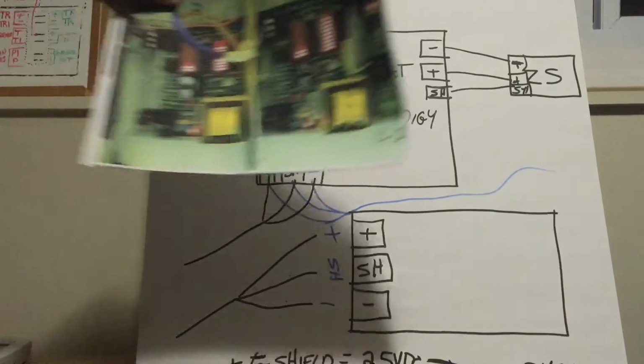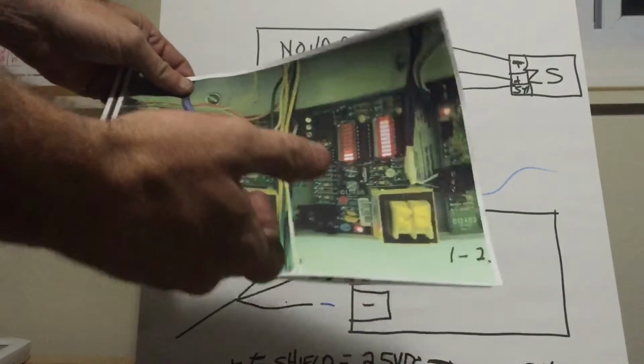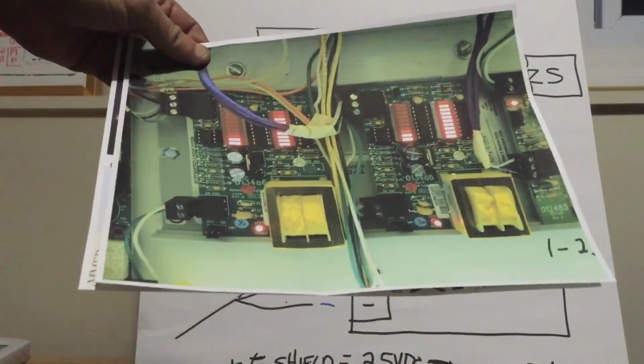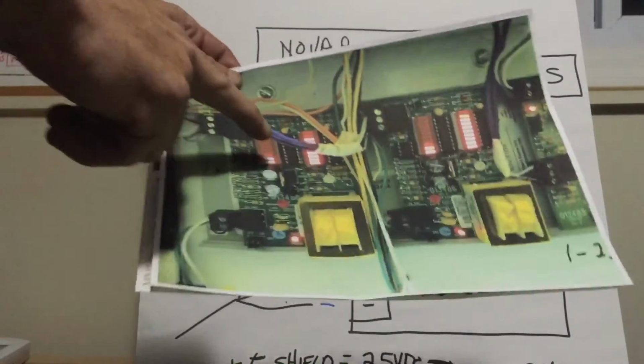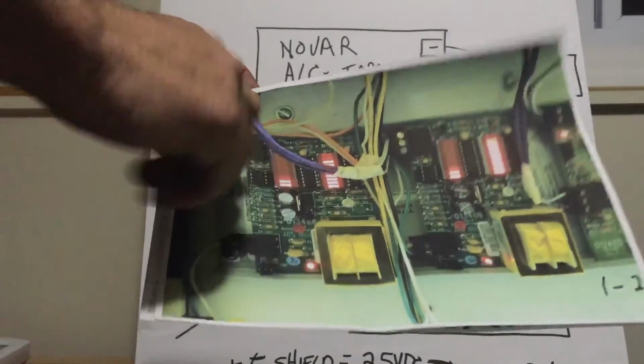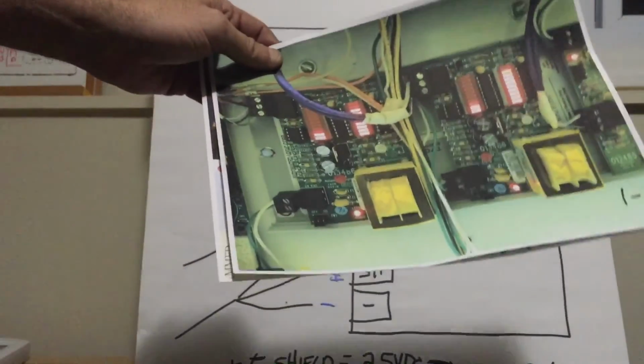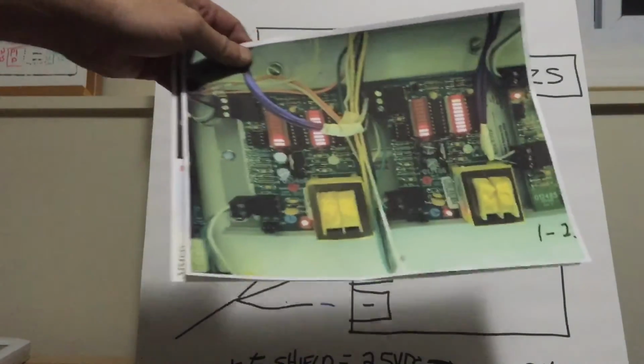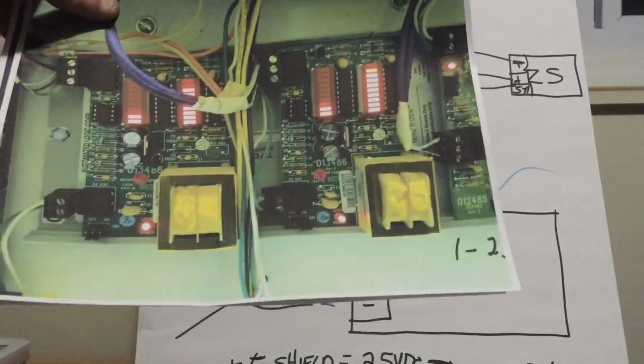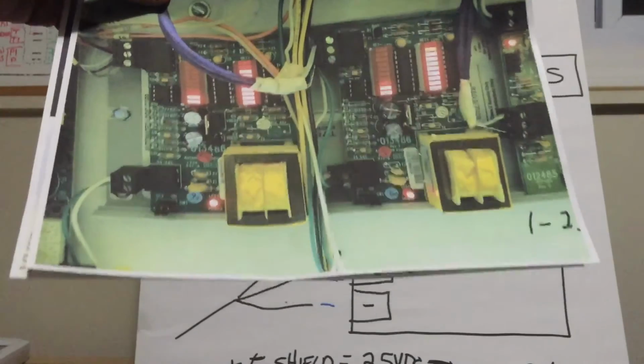Most of you guys know this, but this is what they call a diag or a repeater. These are in the IOP panel, but they also put these in a couple 3 units on the roof. They put them toward the middle or the end of a string. They monitor or diagnose the noise on the line, and they also add a little bit of voltage at a slightly different frequency, and it raises the communication protocol so that it gets above the noise.